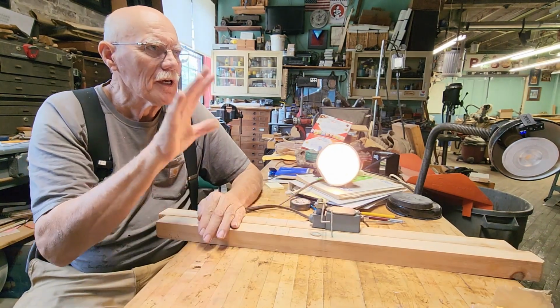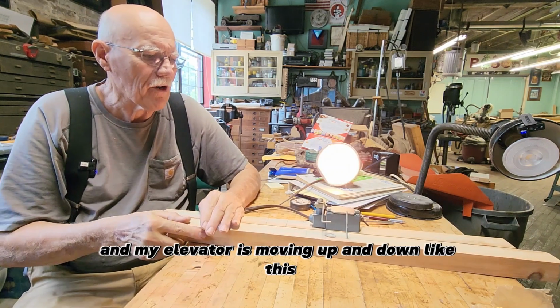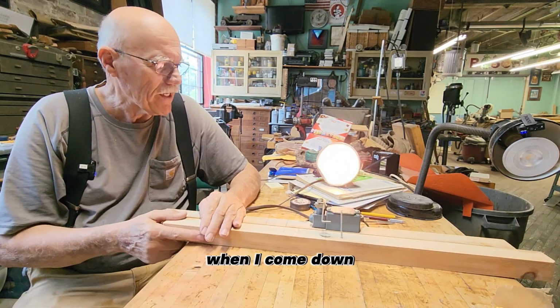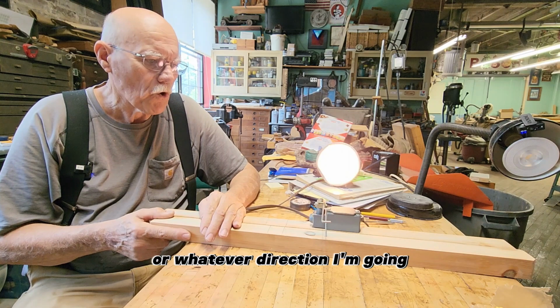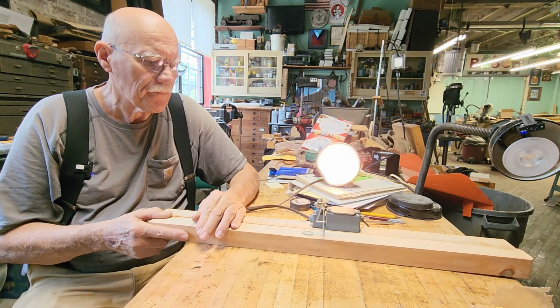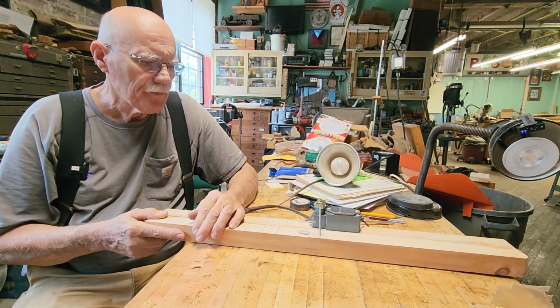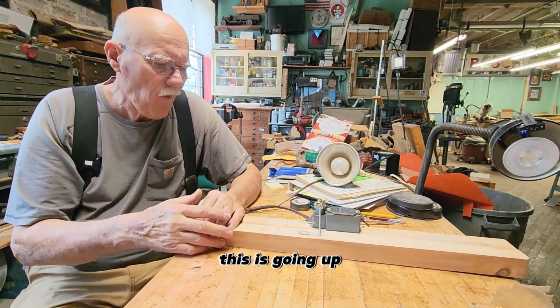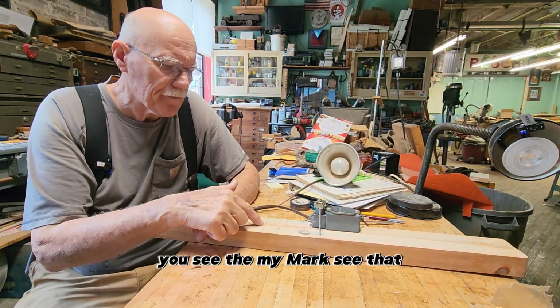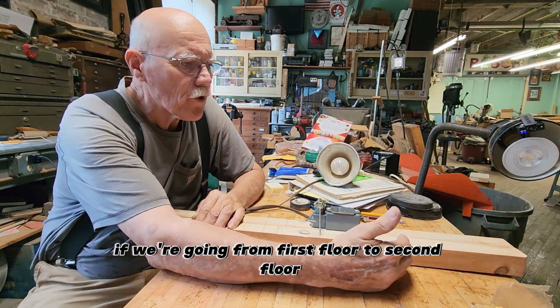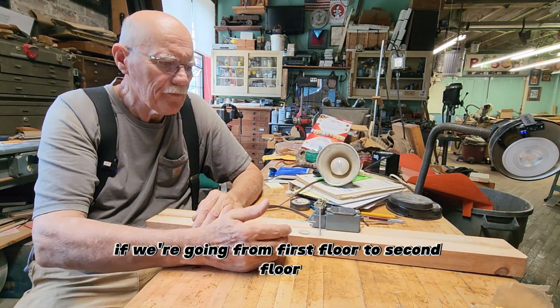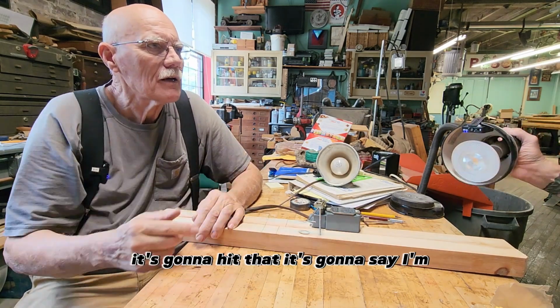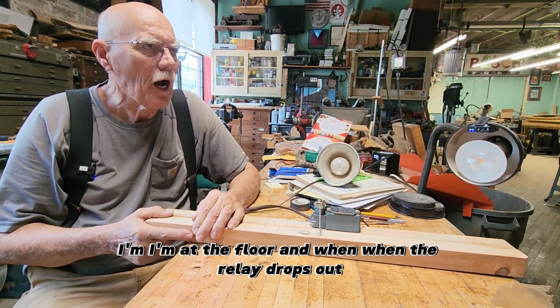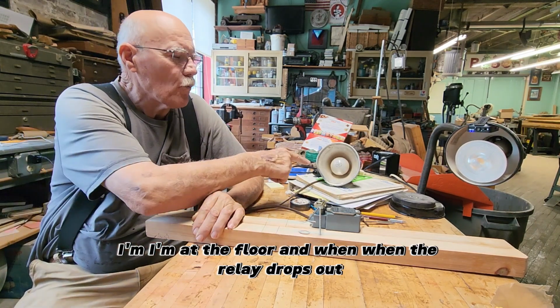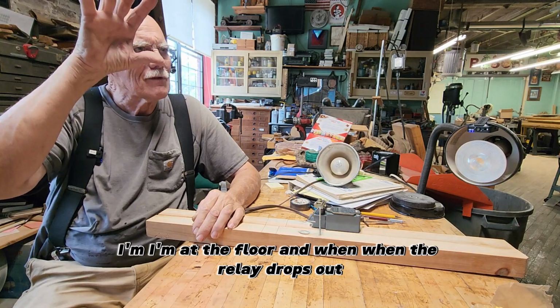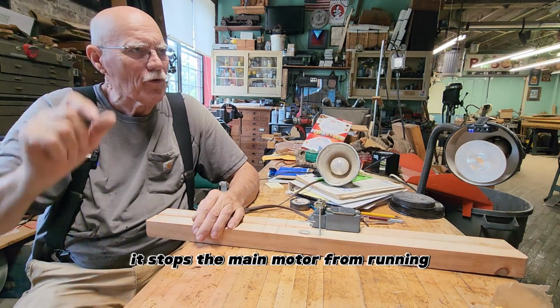limit switch, and it's fastened to the wall, and my elevator is moving up and down like this. When I come down, or whatever direction I'm going, and I hit the switch. See there? This is going up. You see my mark? That's where the floor stops. If we're going from first floor to second floor, it's going to hit that, and it's going to say, I'm at the floor. And when the relay drops out, it stops the main motor from running.